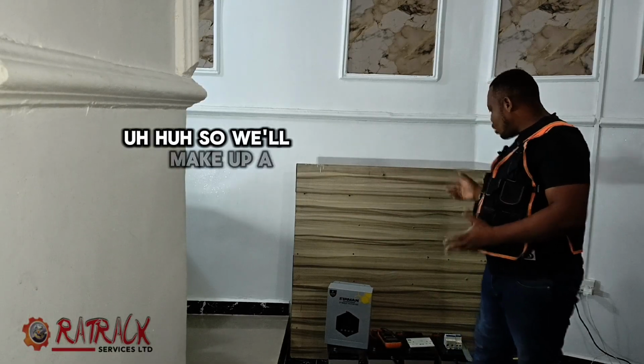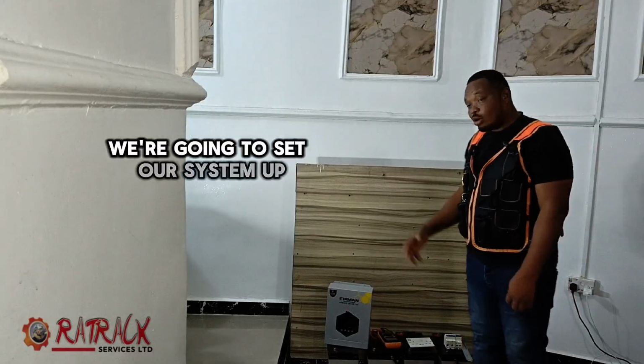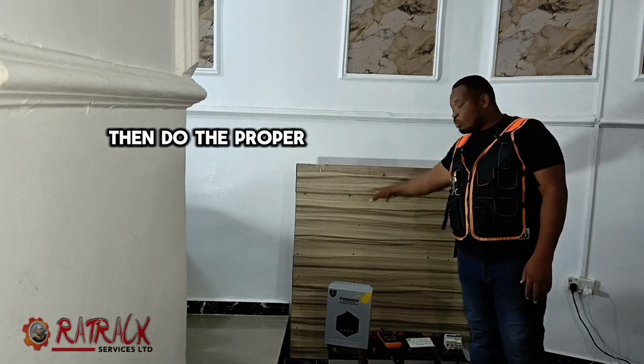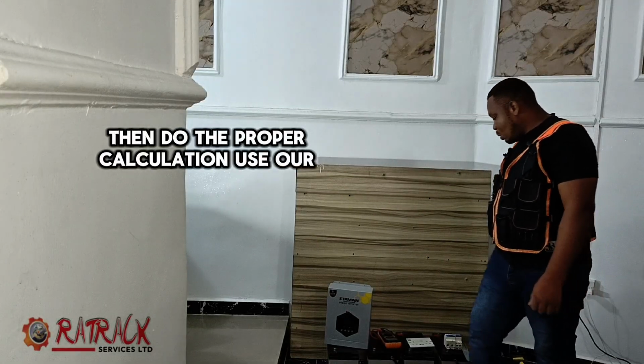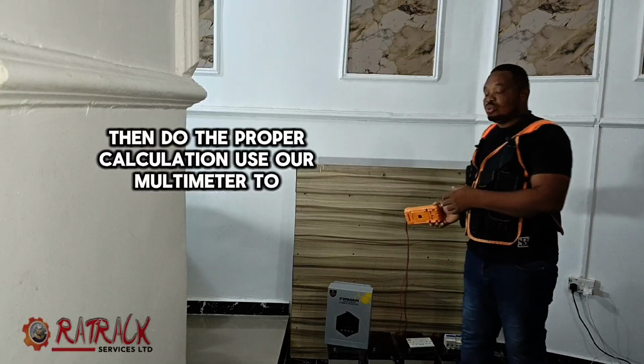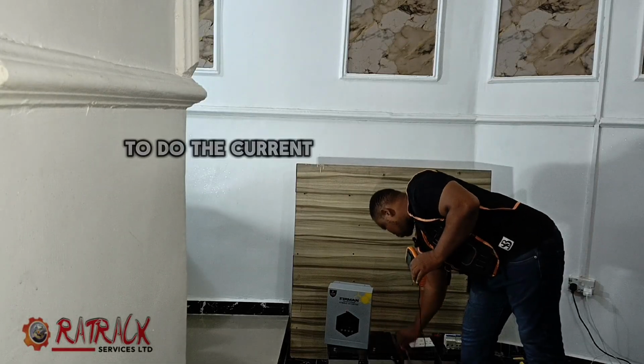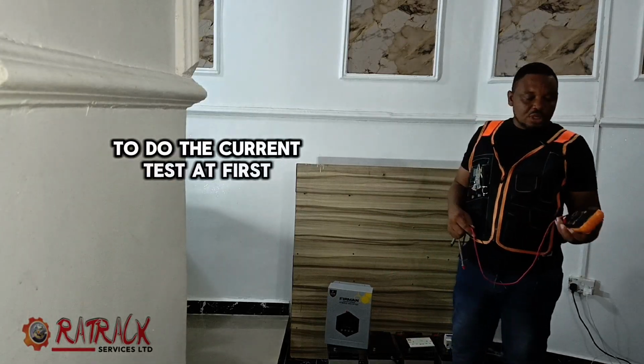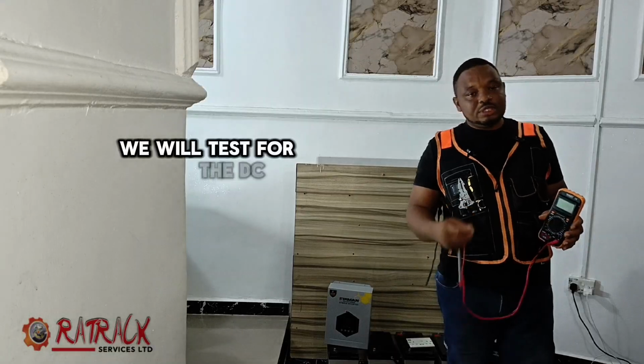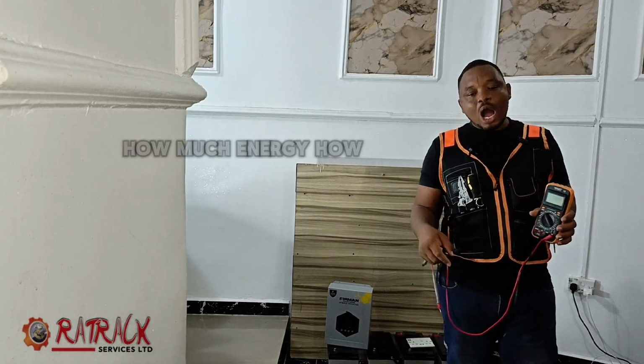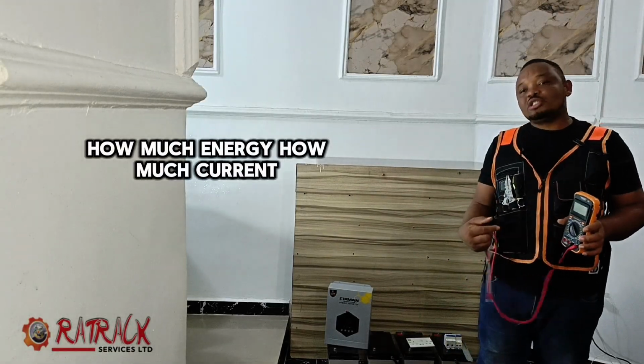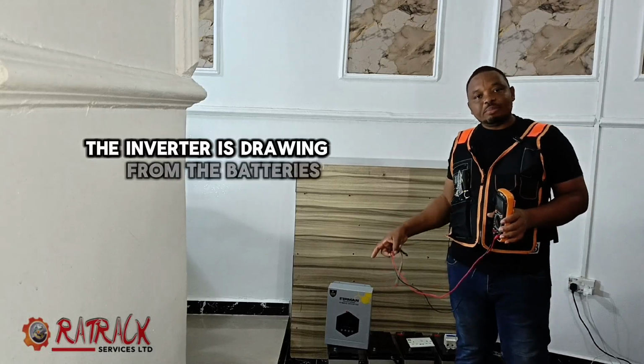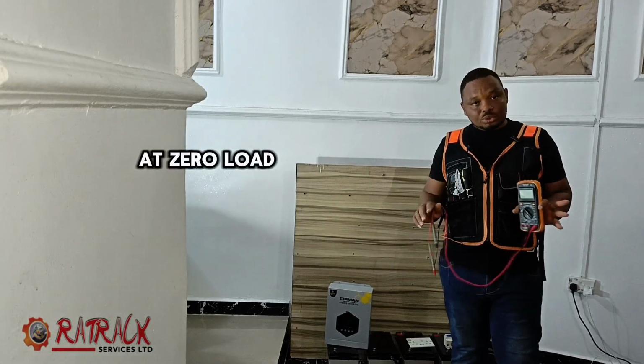So we'll make up a setup. We're going to set our system up, then do the proper calculation, using our multimeter to do the current test. First, we'll test the DC side, how much current the inverter is drawing from the batteries at zero load.